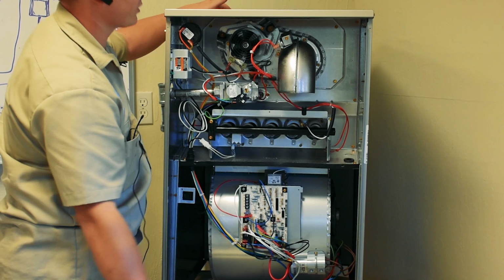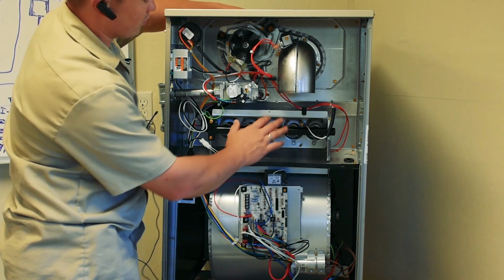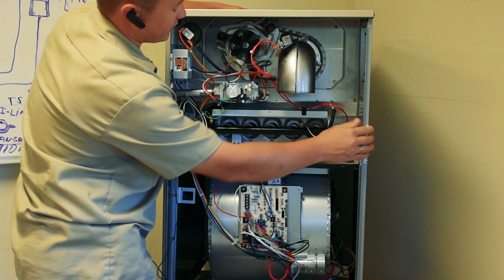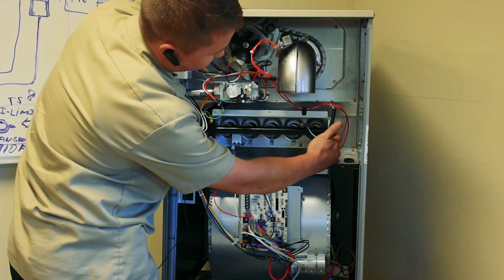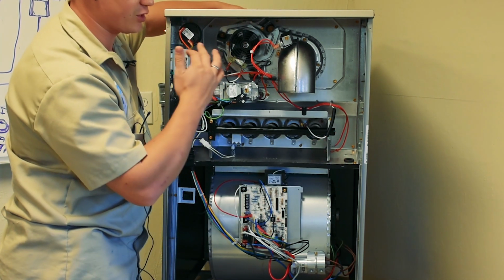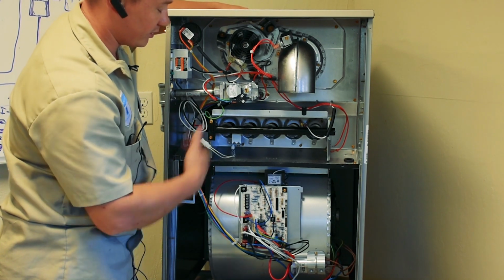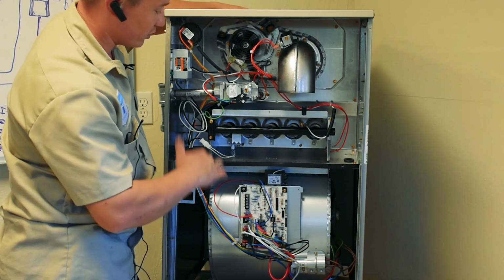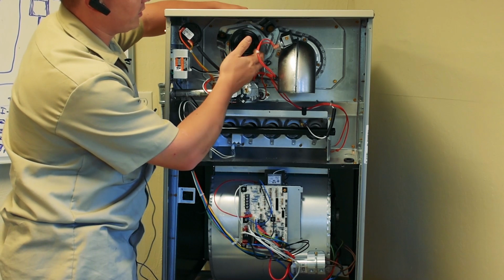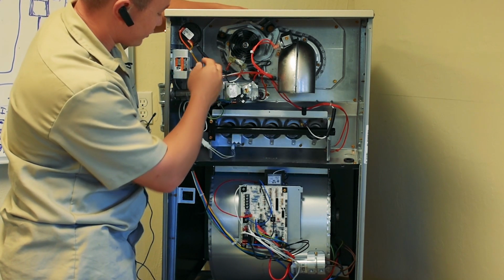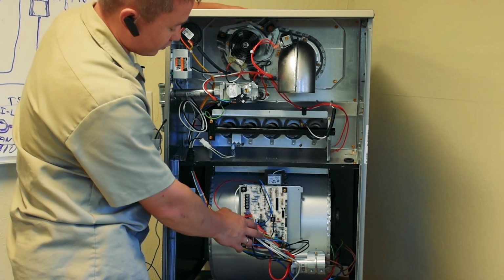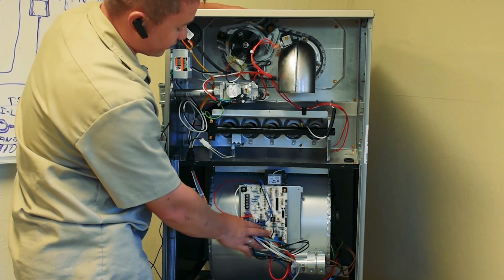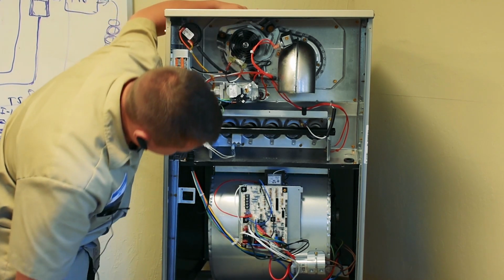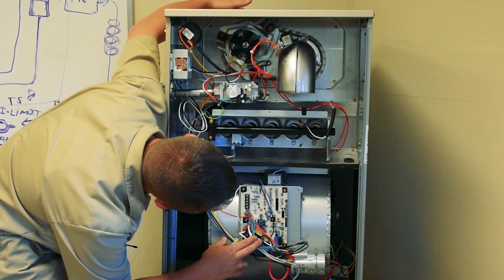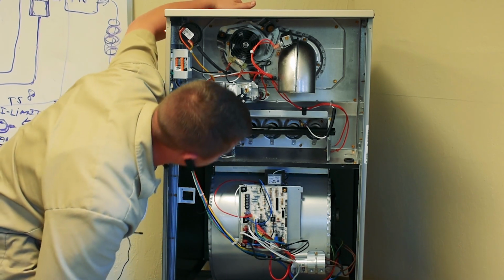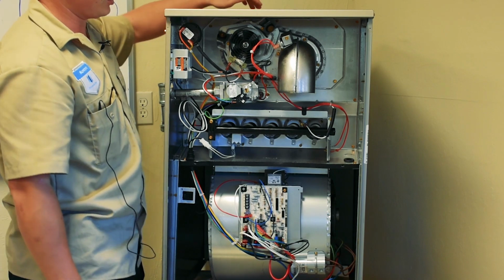Because when the furnace is running, for example, if your heat exchanger gives too much heat to the body, to the frame of the furnace, then this heat will reach these safety thermostats and it will cut off the whole circuit for running the furnace. It just will not turn on the whole furnace. It will try to run the inducer motor multiple times, but the circuit for the pressure switch will be turned off. And you will probably be able to see the issue at the control board. Here is a small indicator which will tell you the issue, what could be wrong, like a pressure switch issue or something like that.